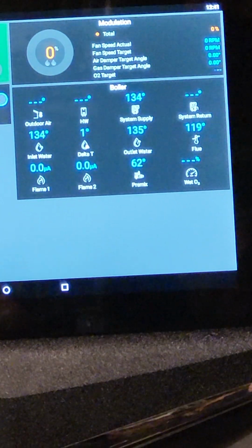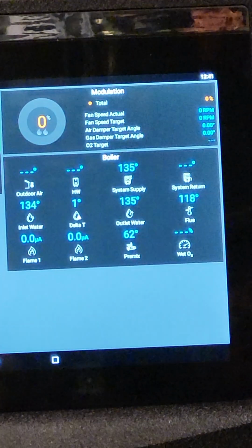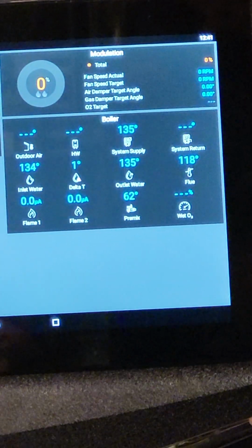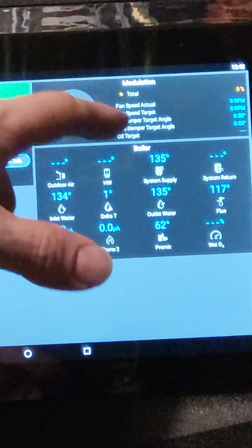All right, so main control, we got the green box. That means everything's normal. You can see the little modulation screen up here. It tells you what the fan speed actually is, 0 right now because it's not running, and then what the target is, so what it's shooting for and what it actually is. It's got our air damper angle, and then our gas damper angle, and then our O2 target, which won't show up obviously until it's running.